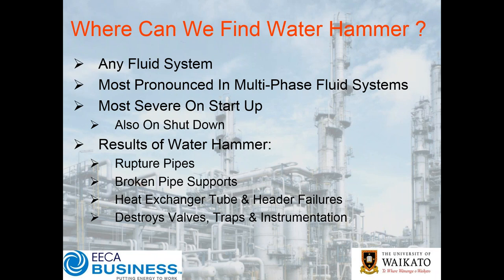If you're relying on instrumentation — especially from the point of view of process control where pressures might be really important — those pressure gauges could be exposed to very sudden spikes in pressure, which can damage the sensitivity of the equipment and ultimately affect their accuracy, which can then impact your process. So if you walk around and hear banging, you want to be looking for broken pipe supports. If you're already past that point, you really need to be doing something. If you don't act, it is literally a matter of time until you have a rupture somewhere.